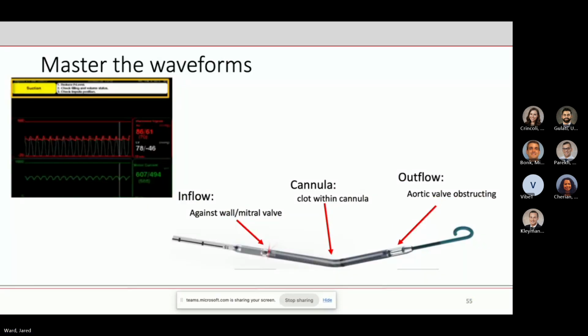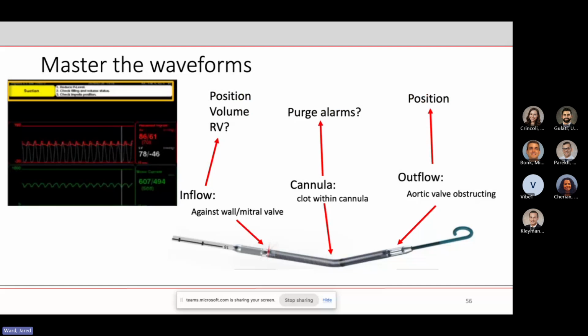These things can basically get suction events from three different problems. One, at the inflow, because it's against the ventricular wall, or it's against the mitral valve, or your preload is too low. Two, you develop a clot within the cannula itself. Or three, there's obstruction of the outflow because it's sitting right on the aorta. It's just too deep. So in the inflow problem, it's positioning. Is it a volume issue or preload issue? If it's a clot within the cannula, your purge alarms are going to be off. And you should be able to figure this out generally easily if it's an outflow tract problem, just by putting the probe on the chest.